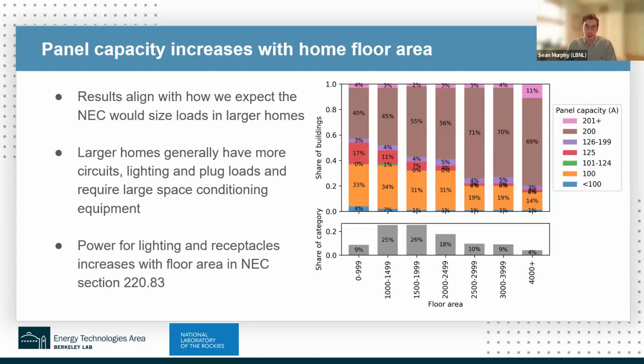Next we show panel capacity and how it increases with home floor area. As the figure shows, the share of 200 amp panels increases as we increase the floor area bin, while the share of 100 amp panels declines accordingly. This aligns with how we'd expect the NEC to size loads in larger homes, since larger homes have more circuits, more lighting, and require larger HVAC systems. The NEC load-based method also takes floor area as an input for estimating lighting and plug loads, so this alignment indicates our model is picking up on the expected behavior of the National Electrical Code as it applies to the building stock.